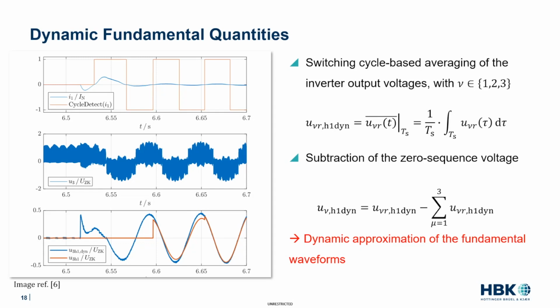And if you have a pulse width modulation which includes some zero systems, for example third harmonic injection or also other flat top modulation, then it would be necessary not only to calculate in the first step the average of the inverter output voltage based on the switching cycle, but in the second step to subtract again the voltage zero system. If you use the ideal star point, this is subtracted automatically.